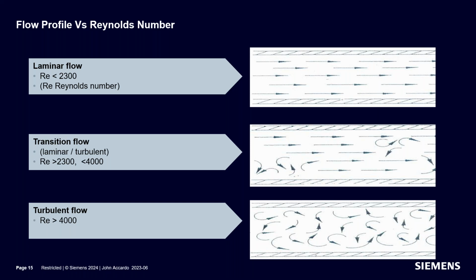Laminar flow is basically if you have a viscous fluid or you're at a very low flow rate, the fluid just travels down the pipe in layers or lamina. And it's a nice smooth condition. But as you increase flow, or if the viscosity is lower, those layers break down. The friction between the layers starts to cause turbulence, and the fluid starts to tumble and spin and travel down the pipe in a turbulent fashion. And the majority of the applications that we see are in fact in the turbulent flow regime. But we don't care. You can be laminar, you can be turbulent, doesn't matter. The meter will correct for it.